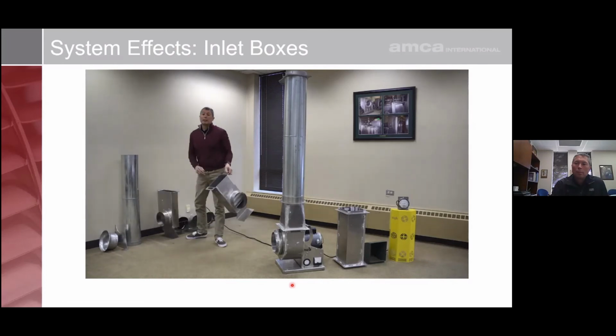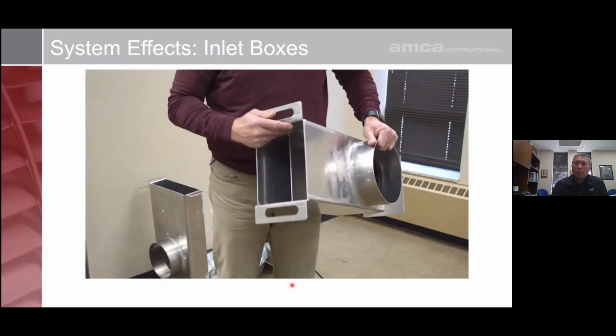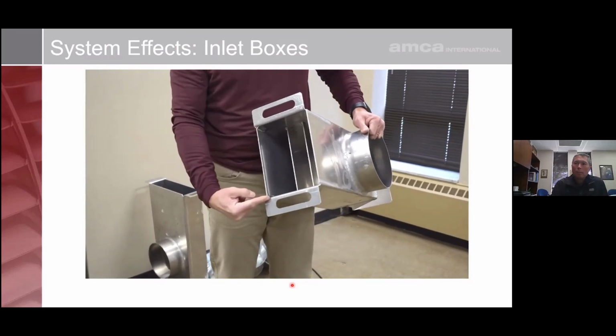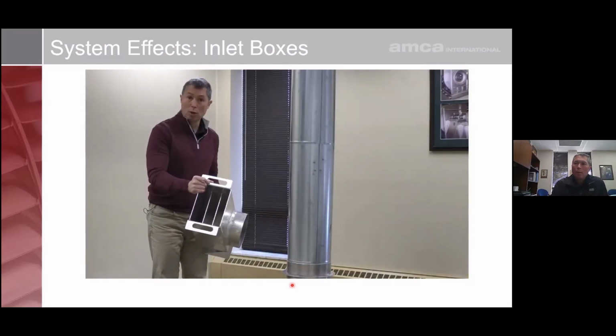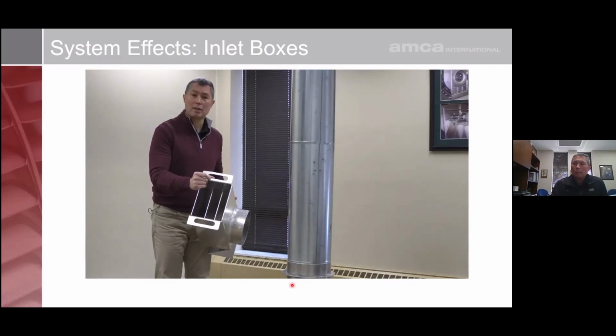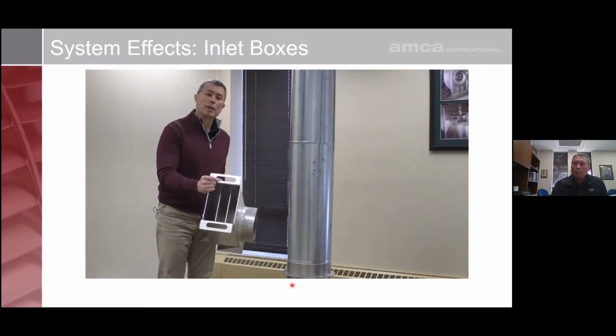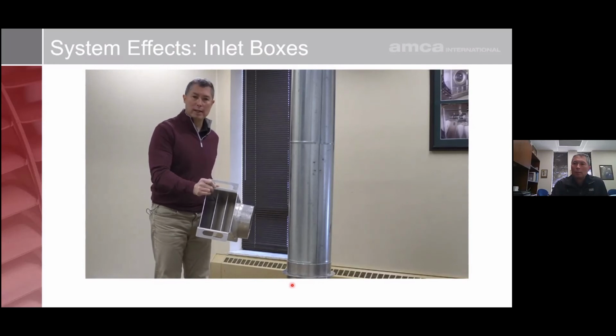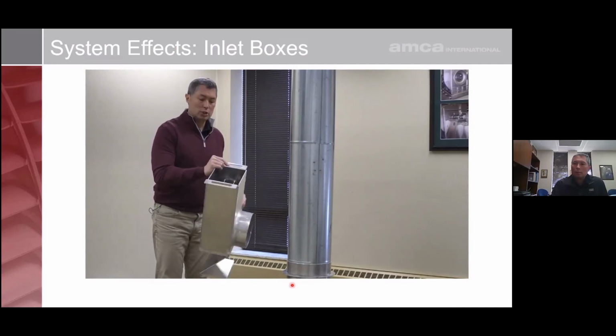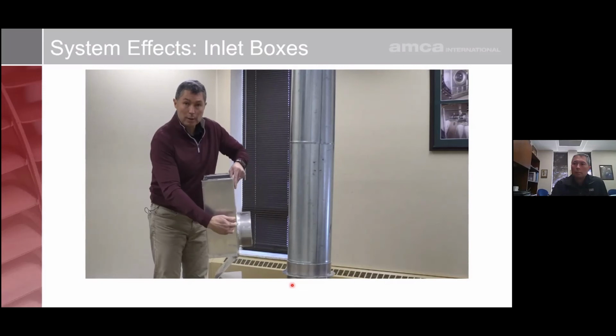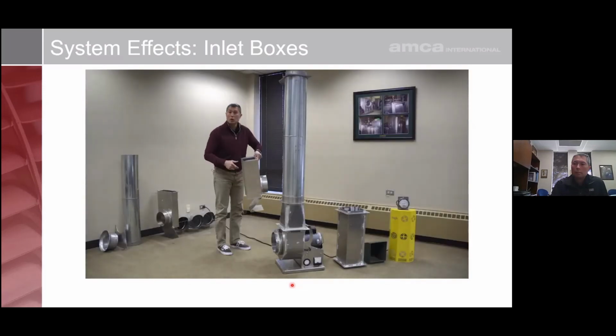Now here we have an inlet box that's a little bit better designed. Its aspect ratio is much more square. Its depth compared to its width is much more on the square side of things. It's not an elongated rectangle. The other thing you'll notice is that we've added turning vanes to this inlet box. Turning vanes, just like with the 90-degree elbow, help efficiently load the air as it goes into the fan.